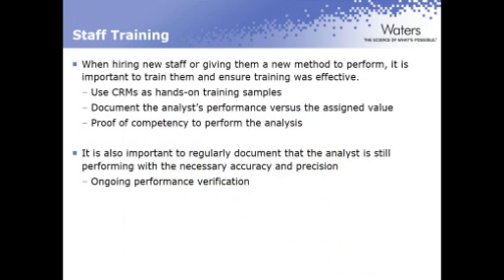Well, how's the best way to do that? We can use a CRM because, if we remember, the certificate that comes with that CRM gives us not only the actual certified value of the parameter or parameters they're testing for, but generally also an acceptance range. So by meeting that acceptance range, we can say we think that person is trained well enough to run tests by that method. It's really important to document the analyst's performance against that assigned value. You want to provide some proof that that staff member is competent to perform the analysis that they're performing.